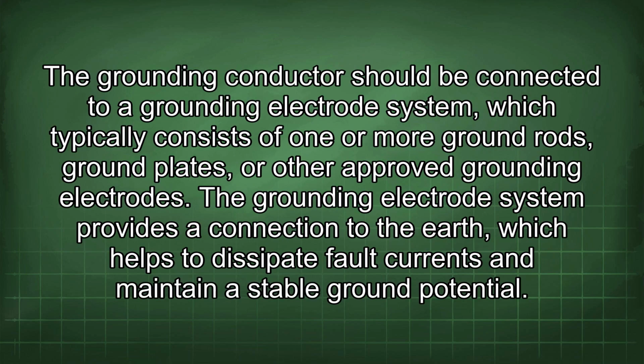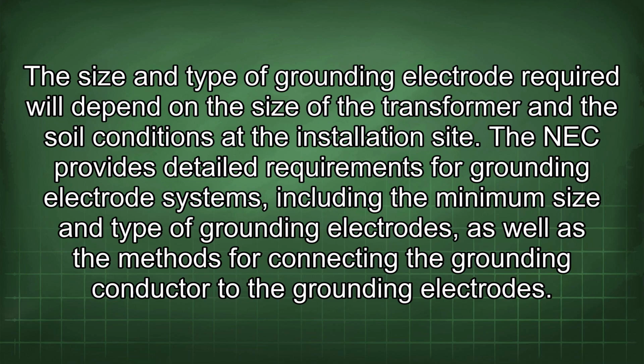The grounding conductor should be connected to a grounding electrode system, which typically consists of one or more ground rods, ground plates, or other approved grounding electrodes. The grounding electrode system provides a connection to the earth, which helps to dissipate fault currents and maintain a stable ground potential. The size and type of grounding electrode required will depend on the size of the transformer and the soil conditions at the installation site. The NEC provides detailed requirements for grounding electrode systems, including the minimum size and type of grounding electrodes, as well as the methods for connecting the grounding conductor to the grounding electrodes.